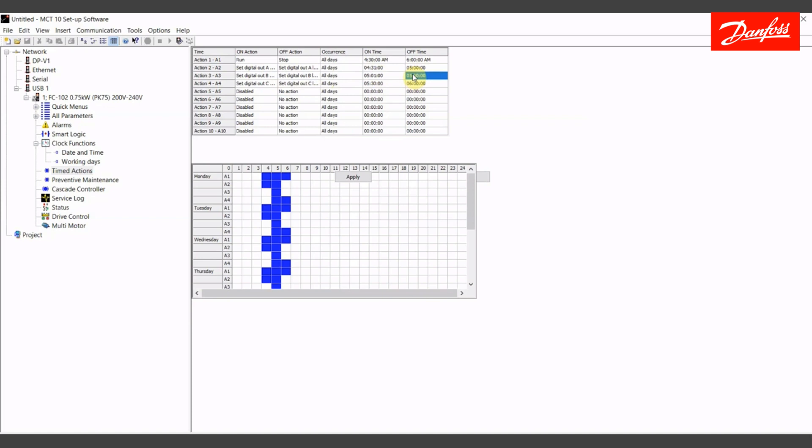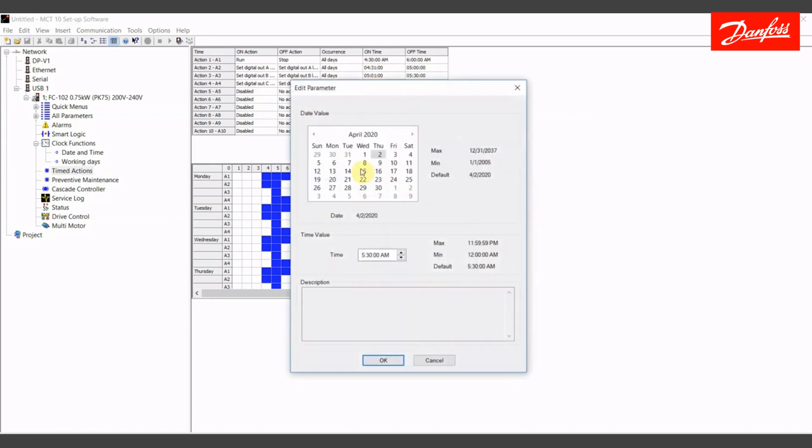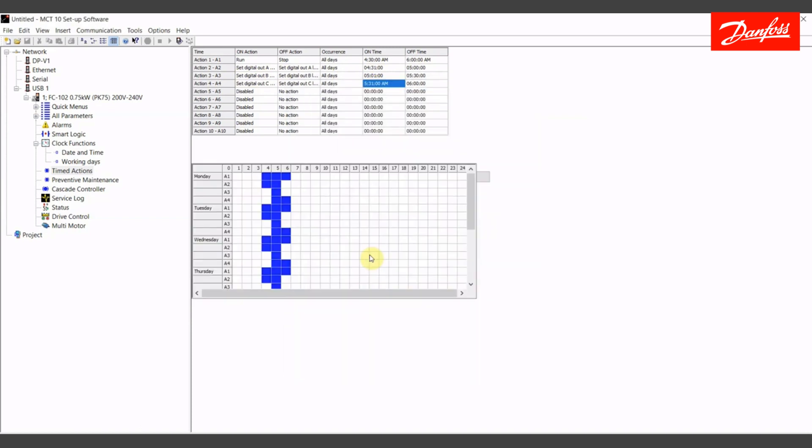I finish up with the final zone C. I am turning that output high, low, from 5:31 a.m. up until 6 o'clock a.m. So I have an hour and a half of runtime, and that is split between the three zones. I have to go and click this apply button that'll appear here, and now that'll be written to the drive. This has been set and written into the drive.